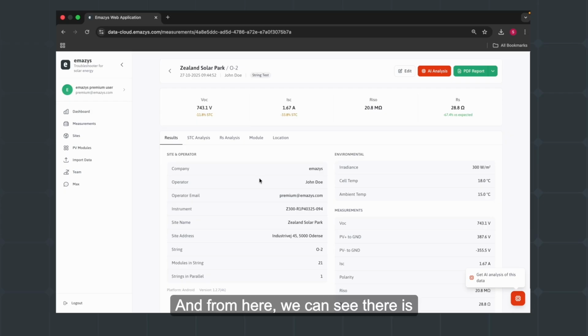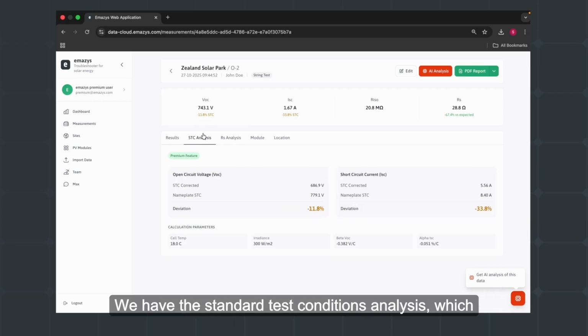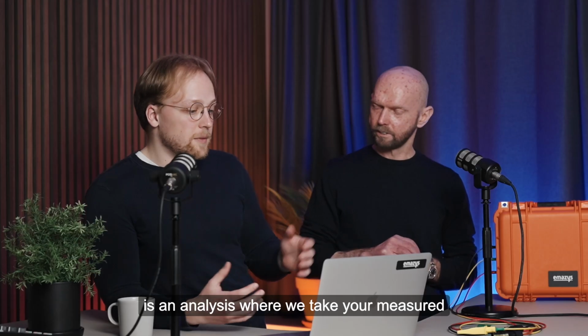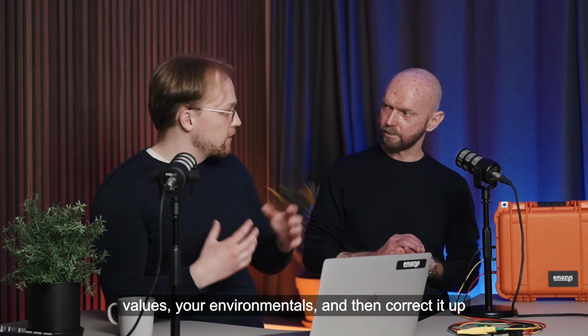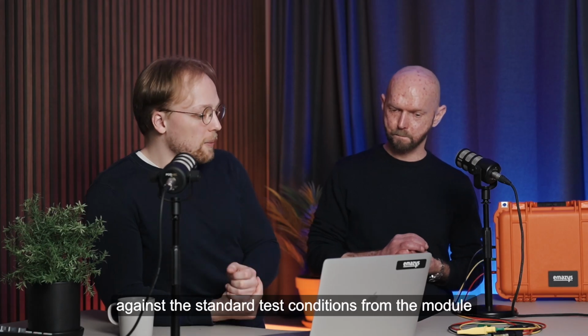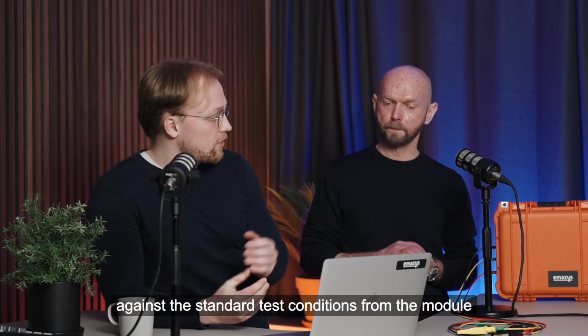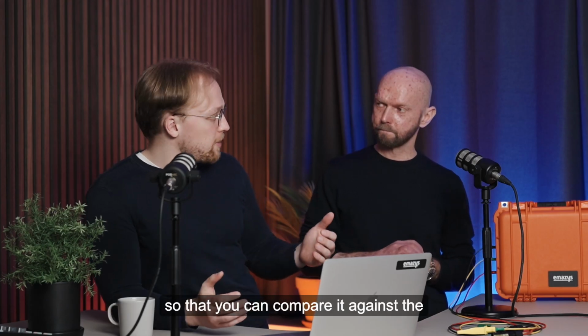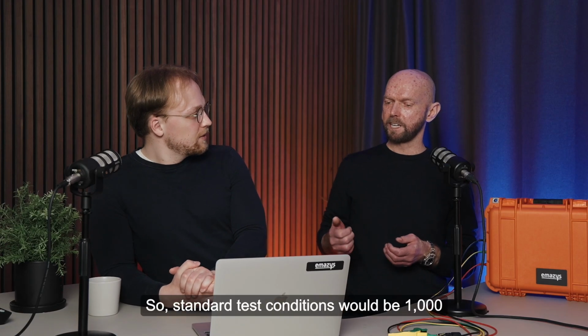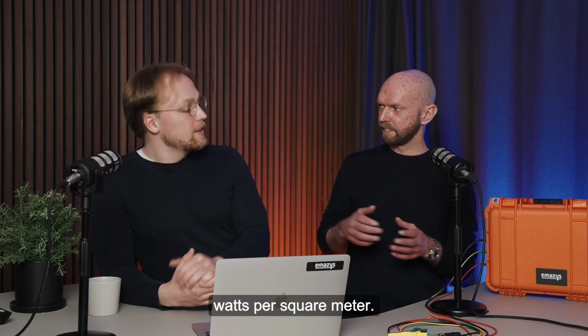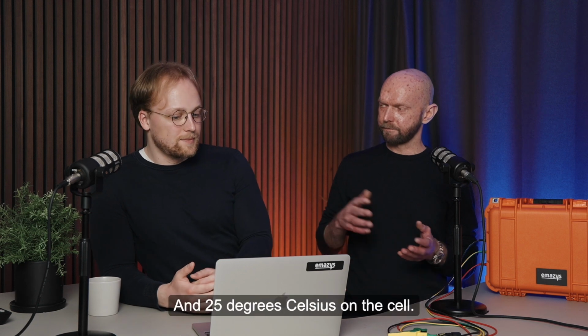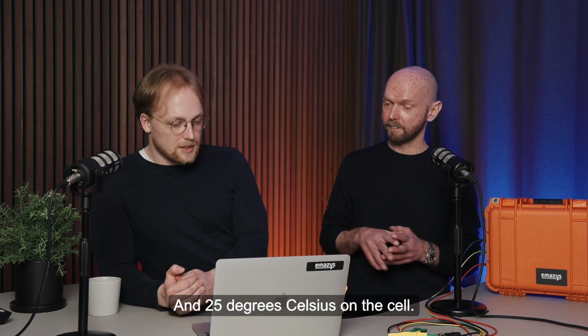Yes. And from here, we can see there are now two analysis tabs. We have the standard test conditions analysis, where we take your measured values and your environmentals, and then correct them against the standard test conditions from the module so that you can compare against the nameplate values. Okay, so standard test conditions would be 1000 watts per square meter. Yes, exactly. And 25 degrees Celsius on the cell.